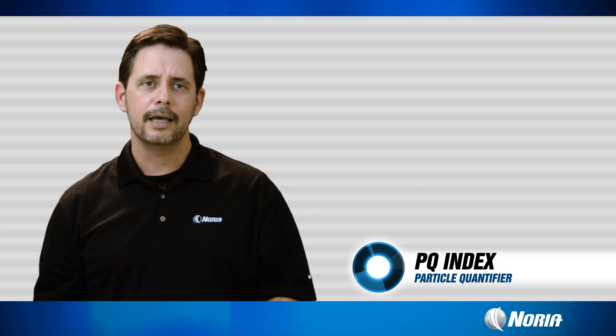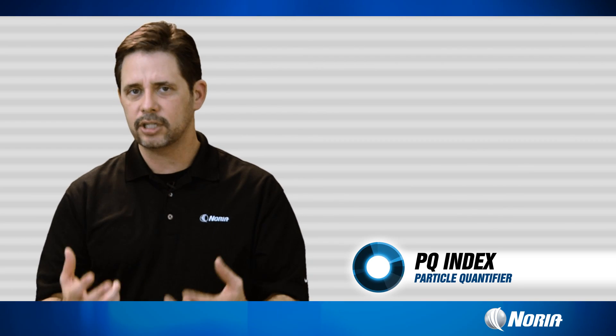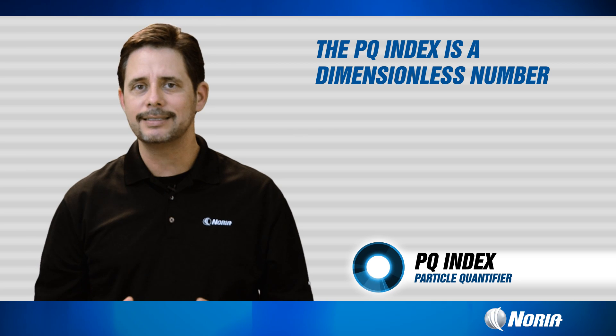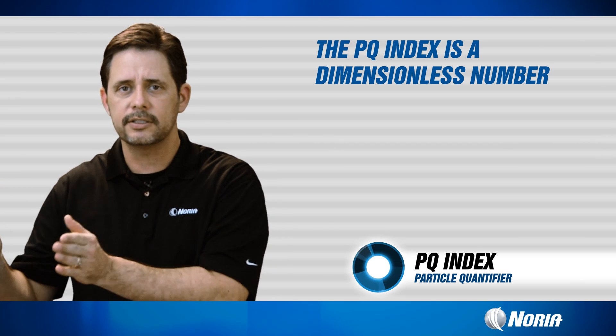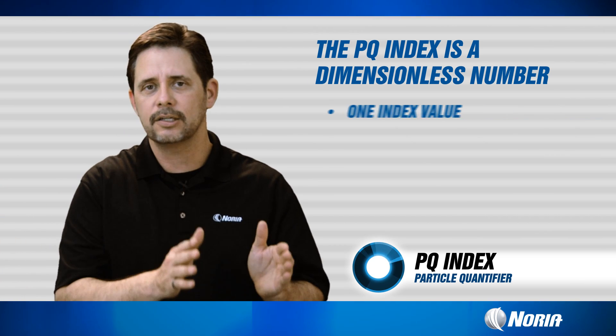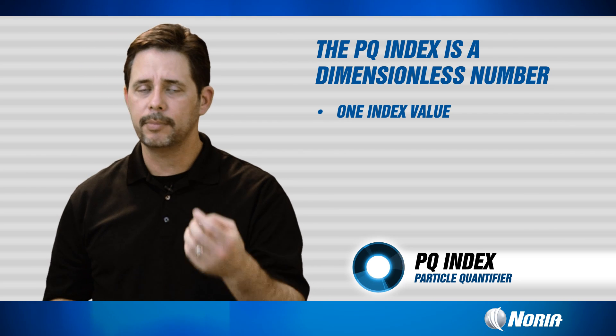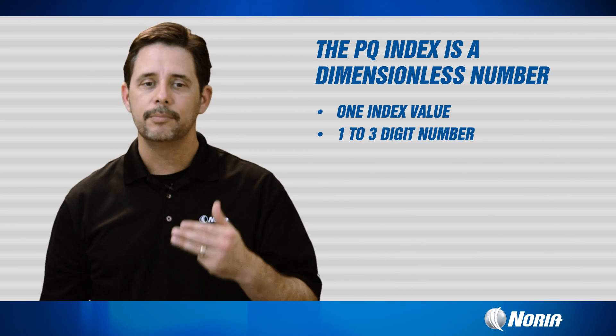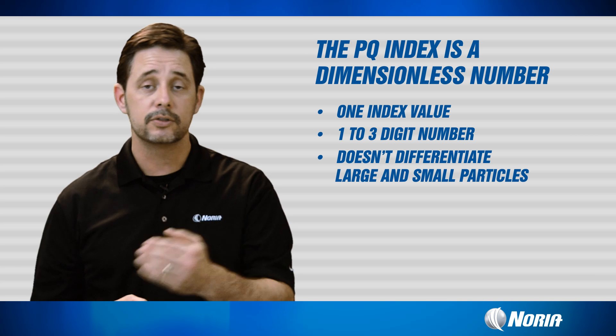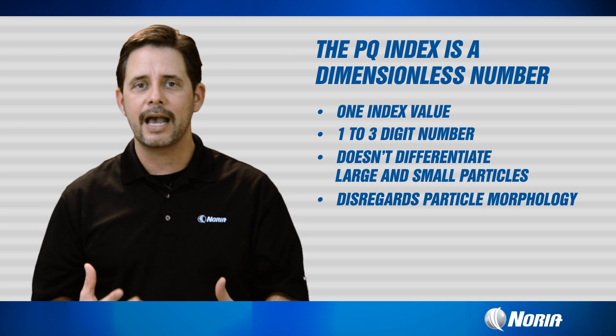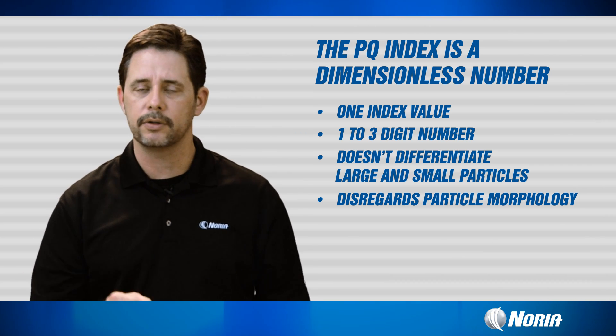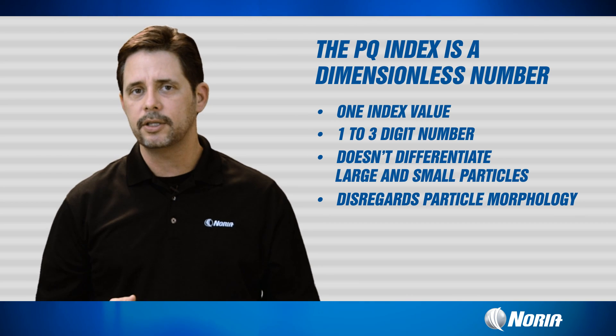Then we have particle quantifier, or the PQ index. The PQ index, like DR ferrography, is a dimensionless number, but that's where the similarities end. DR ferrography gives us two dimensionless numbers — ferrous large and ferrous small — while the PQ index gives us one single index value, which may be one, two, or three digits. The PQ index does not differentiate between large or small particles and doesn't consider particle morphology.